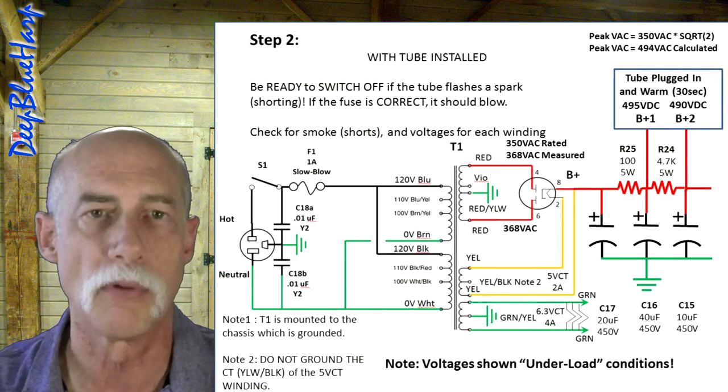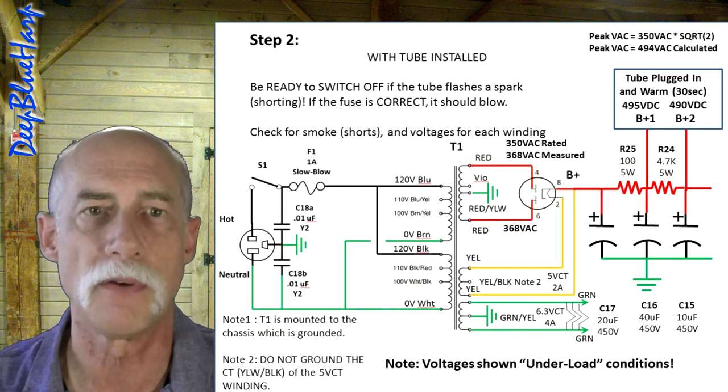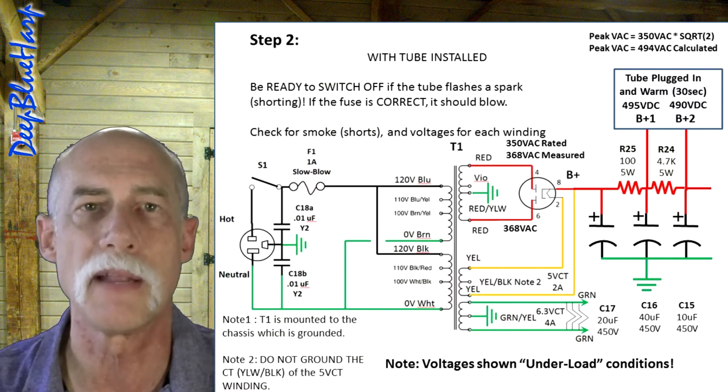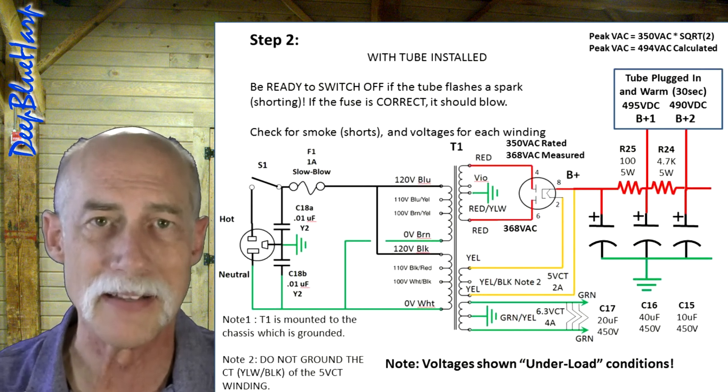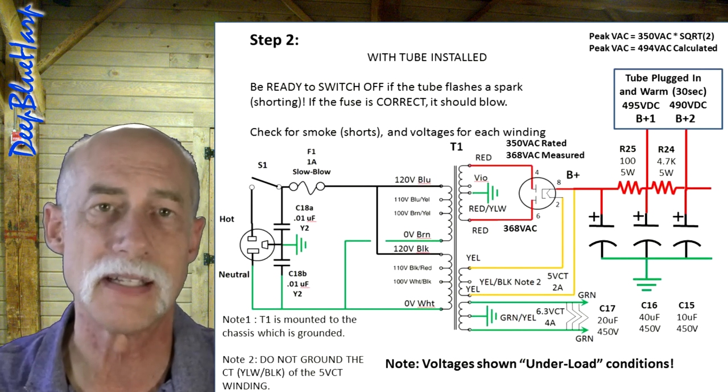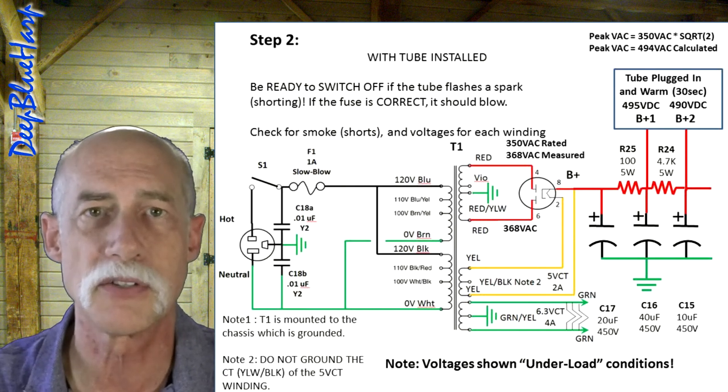But without load, they will float up. You should expect a no-load peak voltage somewhere between 495 and 500 volts. This sums up the test notes for the power supply test. I hope you find this useful.